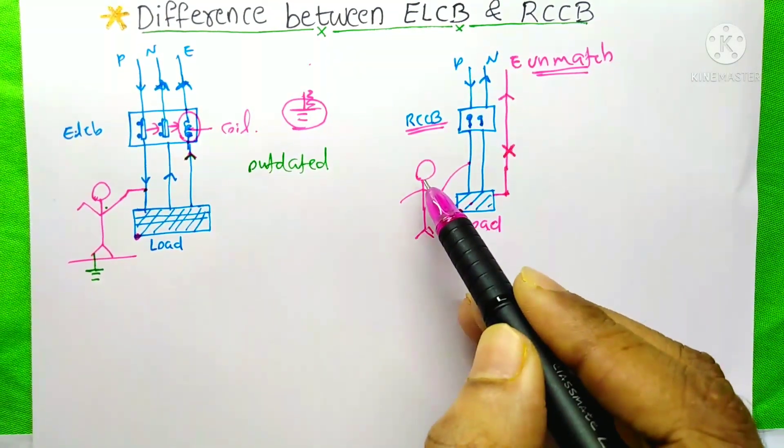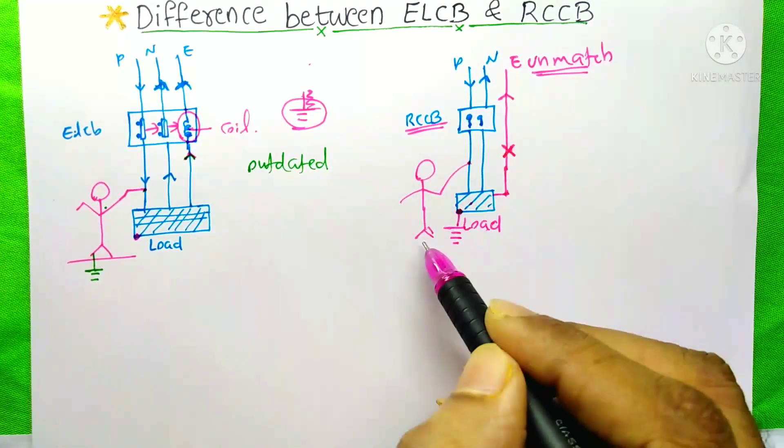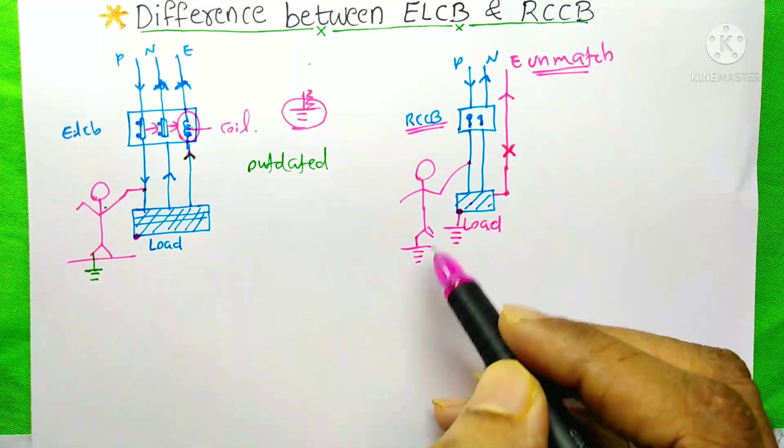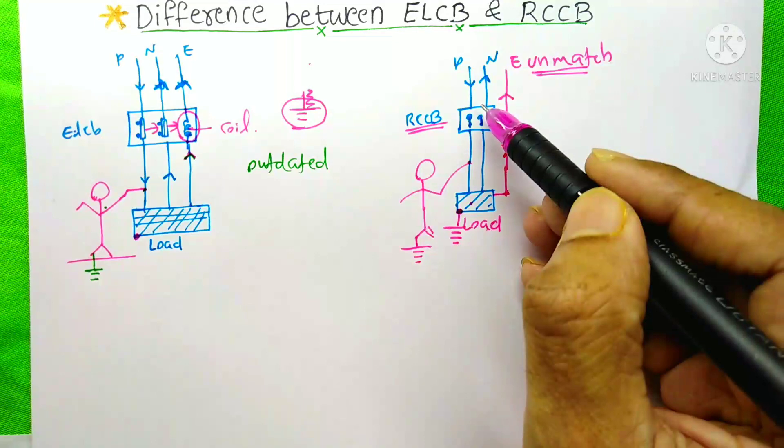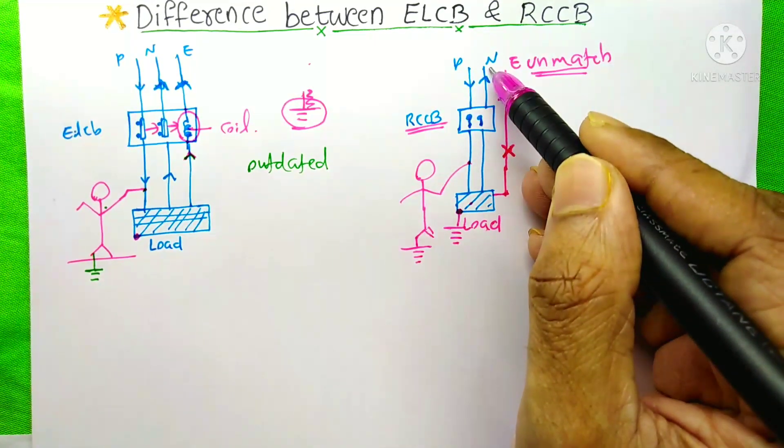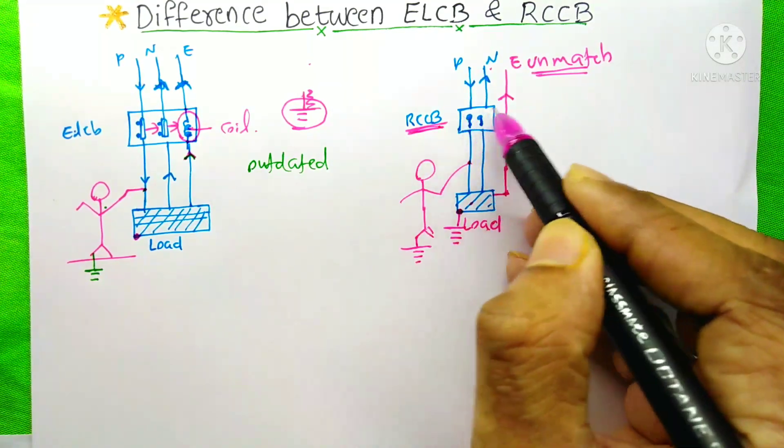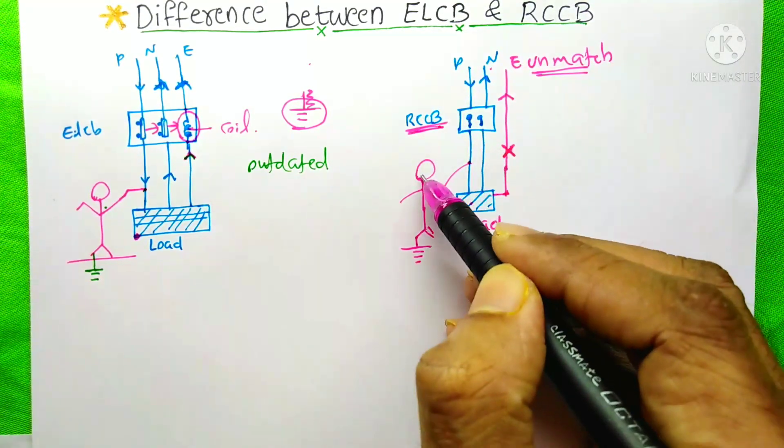Another condition is, if a person touches the phase, then at that time, through his body, the current passes to the earth. At this condition also, the current that comes to this load will not pass through this neutral, and the RCCB will sense that and it will trip the circuit and protect this person.